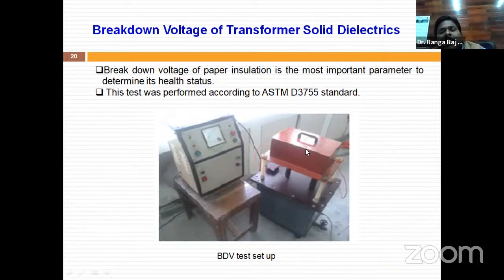Between the electrodes we keep the insulating paper, so whatever stress we apply to the electrodes, the insulating material gets subjected to that stress. This high voltage is developed through this controller, from 0 kilovolts up to 100 or even 150 kilovolts. Step by step we raise the secondary voltage, say 2 kV, 3 kV, 5 kV, 6 kV, and so on up to 60 kV.